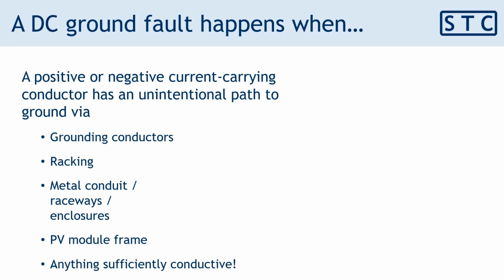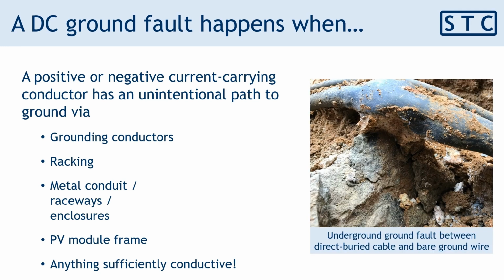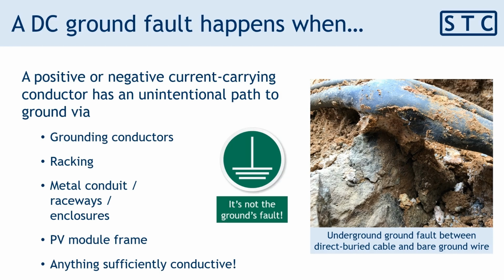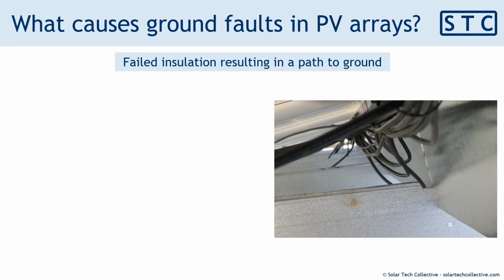In my time in the industry, I've never ceased to be impressed by the number of novel ground faults that I come across or hear about. Here's an example of an underground ground fault between a direct buried cable and a bare ground wire. This is a real tricky fault to deal with. But remember, it's not the ground's fault. The ground's just helping us to identify that there is a fault and that there are electrons flowing where they shouldn't be.